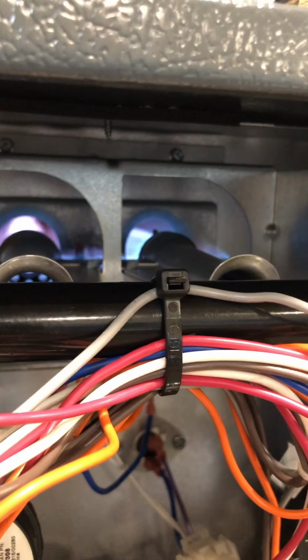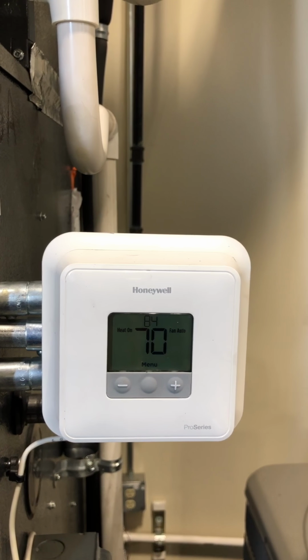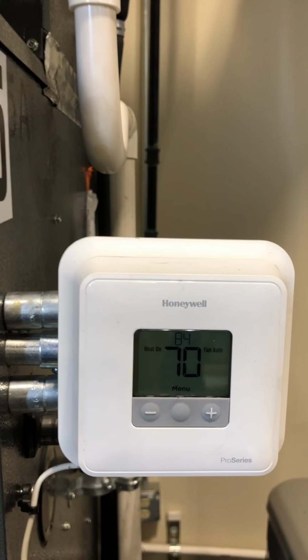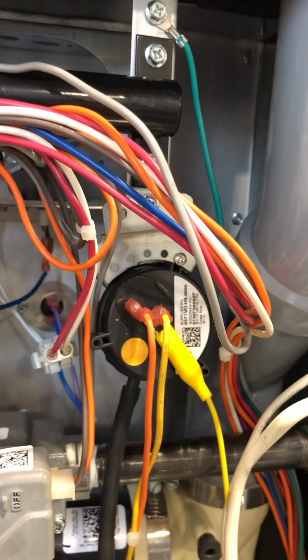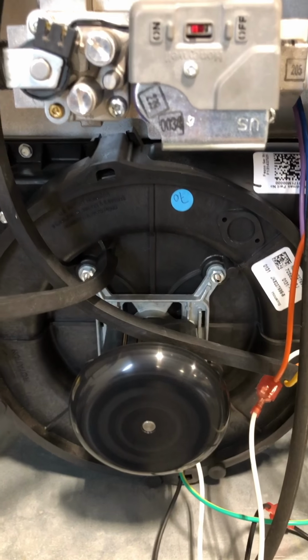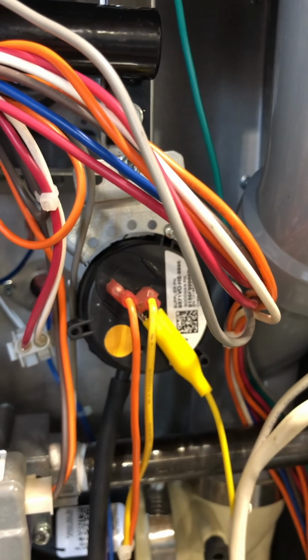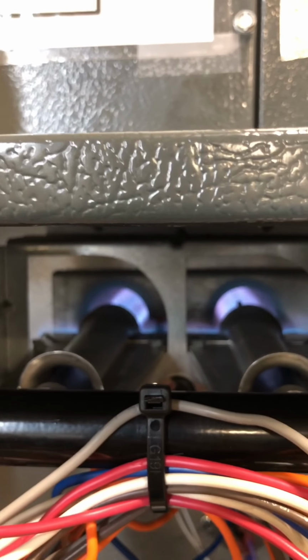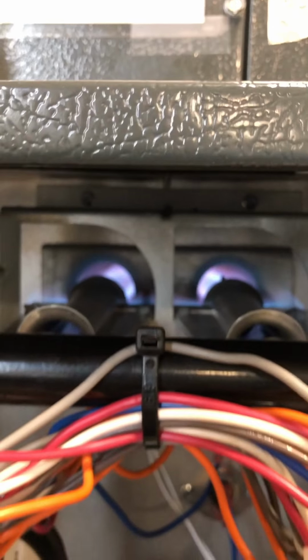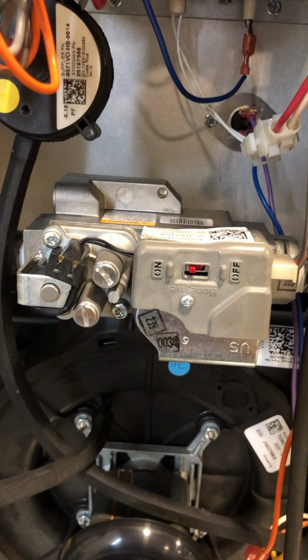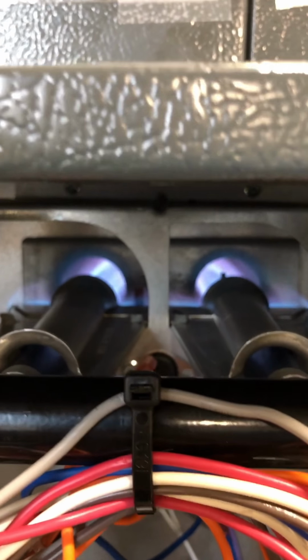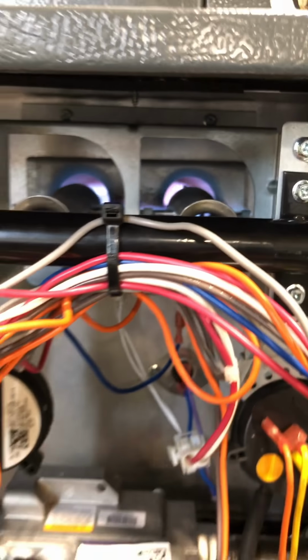As soon as all those are proven, the blower motor will come on after the heat exchanger heats to a certain temperature, and we will resume normal operation until the thermostat is satisfied and kills the call for heat. Operation again is thermostat, verify that pressure switch is open, inducer motor starts, pressure switch will close on vacuum from the inducer motor, hot surface ignition will proceed, it will warm up, 24 volts will be given to the gas valve, gas will pump into the burner chamber and ignite, and our flame sensor will sense flame, our blower motor will fire up. And we're heating.